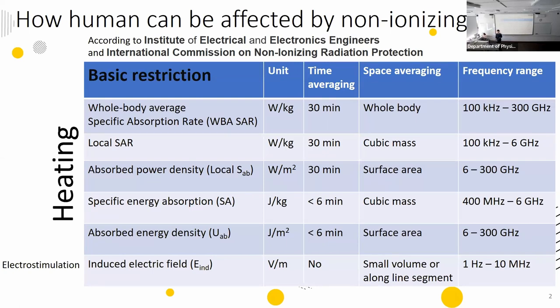Some of these mechanisms require full body modeling in simulation. All of these quantities are called basic restrictions in the standards. To calculate them, you need to model the whole human body in all cases and positions relative to the radio-frequency device. For our WPT problem, it takes a few days to calculate only one position or scale. This is too long for practical use in many cases.